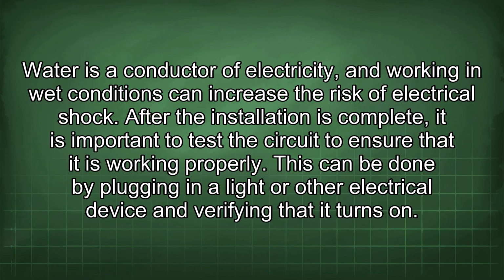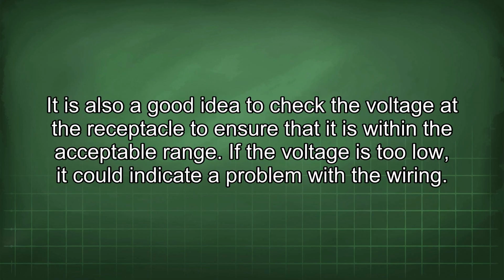After the installation is complete, it is important to test the circuit to ensure that it is working properly. This can be done by plugging in a light or other electrical device and verifying that it turns on. It is also a good idea to check the voltage at the receptacle to ensure that it is within the acceptable range. If the voltage is too low, it could indicate a problem with the wiring.